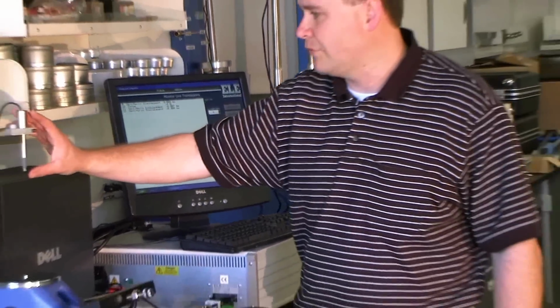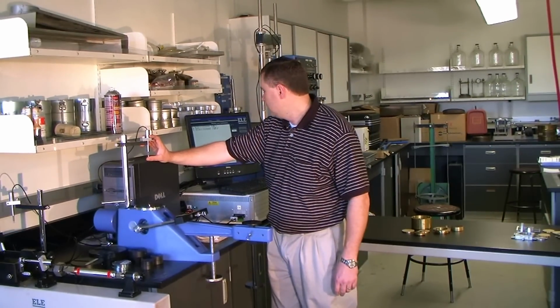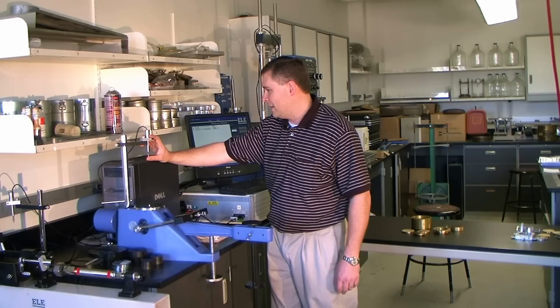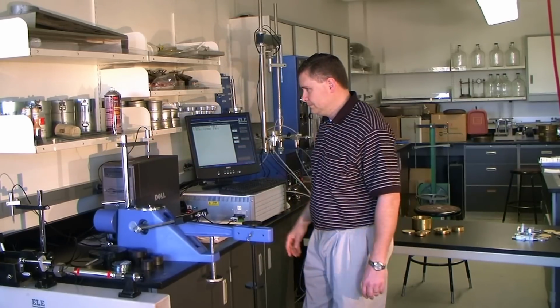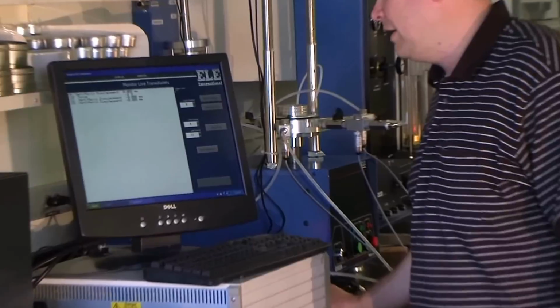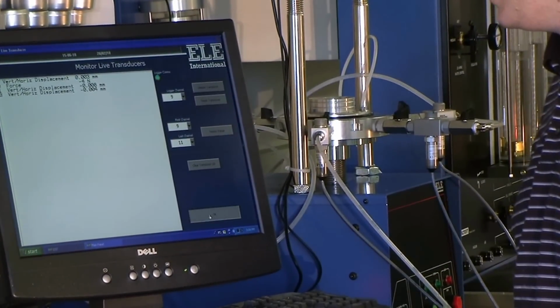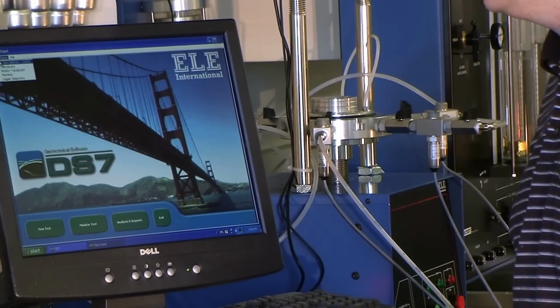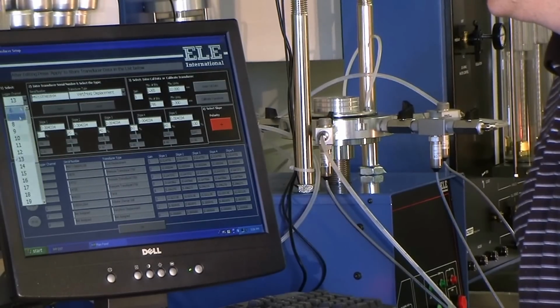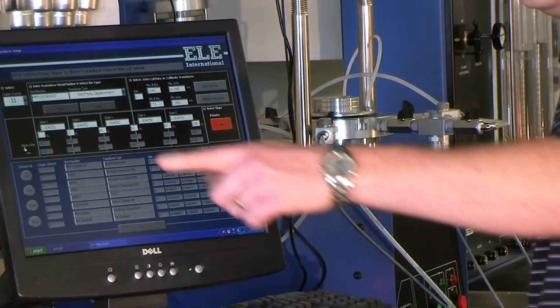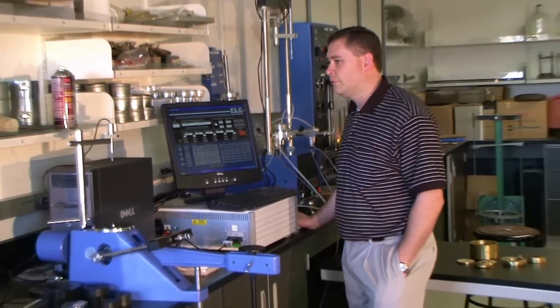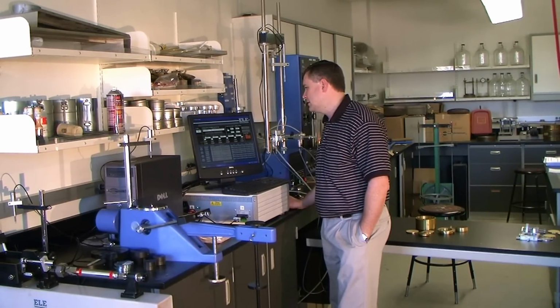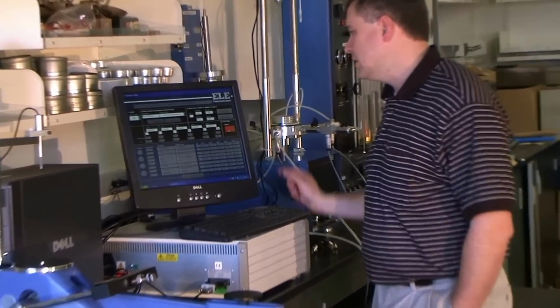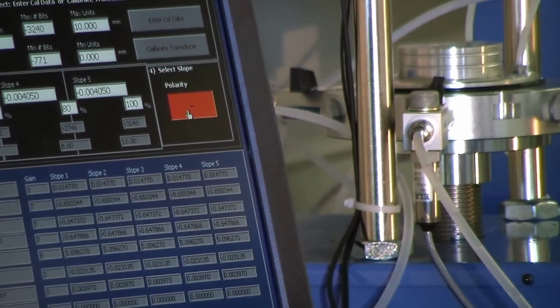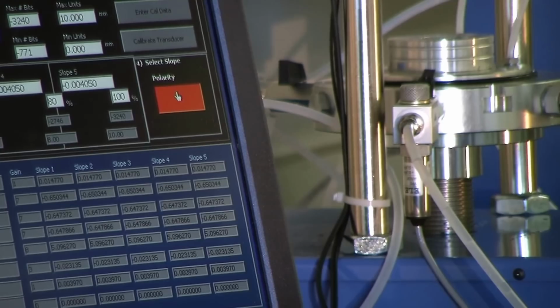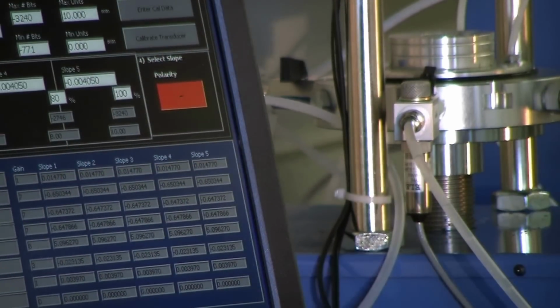Also, the same for this consolidation transducer here. We want it to read positive going down, not up. So we're going to have to put a negative polarity on both of those transducers. So if we click OK at the bottom right, go back to Configure, Transducers, go to channel 11, which is the vertical transducer for the direct shear machine, and they have positive slopes right now. Go to the box number 4, polarity, the bright orange button. Click that until the slopes are negative.